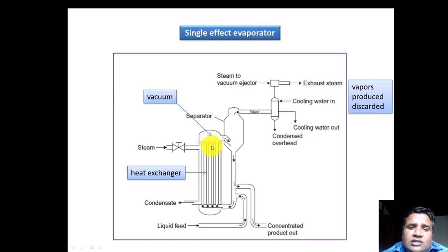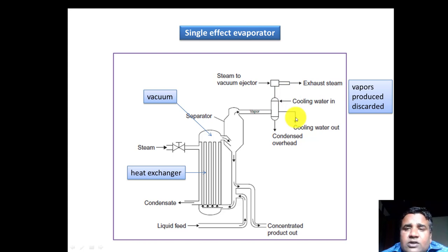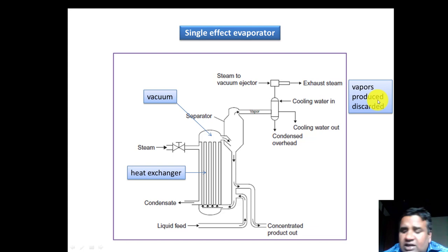The steam circulates and as it loses temperature it condenses; condensate is collected from the bottom. From the bottom we supply the liquid raw material, and upon heating it becomes a mixture at high temperature. In the separator the vapor is removed, and from the bottom of the separator we collect the concentrated product. When the vapor is discarded and not reused, that type of evaporator is known as a single effect evaporator.